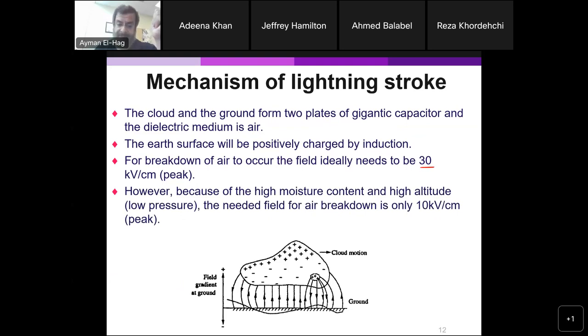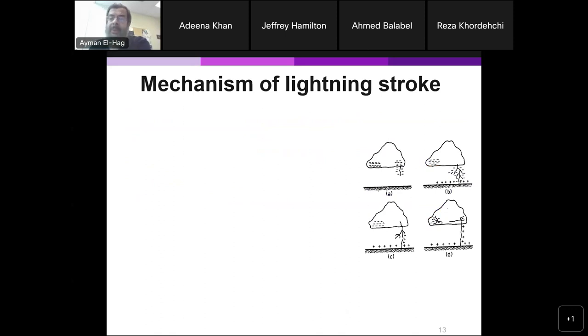However, because of the humidity, and remember, this is a cloud, so the weather is humid. And because of the high altitude, you have a low pressure. When you have a low pressure, you have a lower breakdown voltage. And just as a side note, this is one of the challenges for designing an electrification system for airplanes, because for the insulation material, we always work at ground level. But once you go to high altitude, this changes because of the low pressure. So here the required field to create a breakdown is not 30 kV per centimeter anymore, it is around 10 kilovolt per centimeter. Now let's see what will happen.